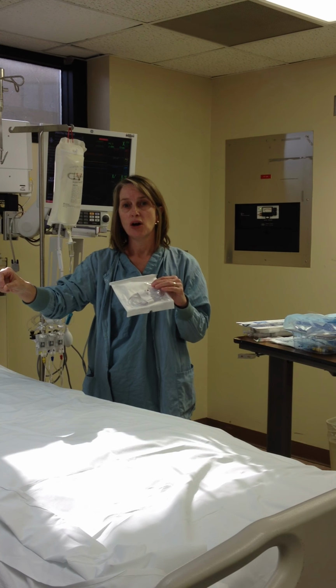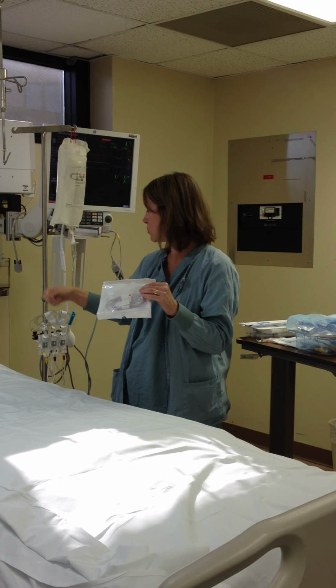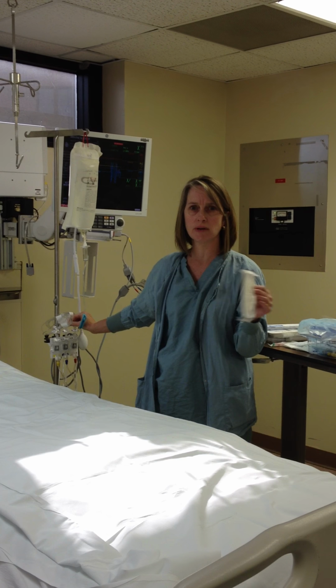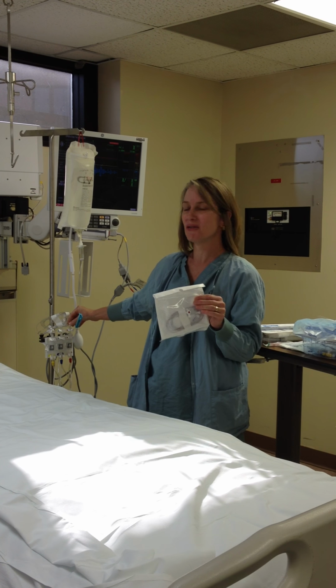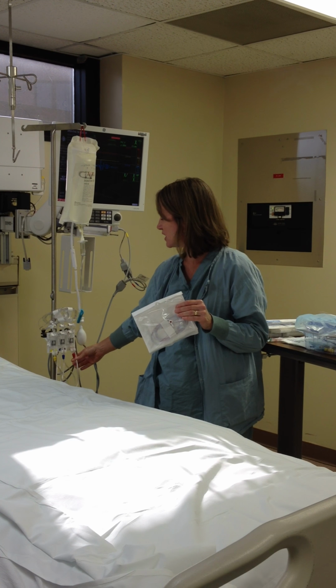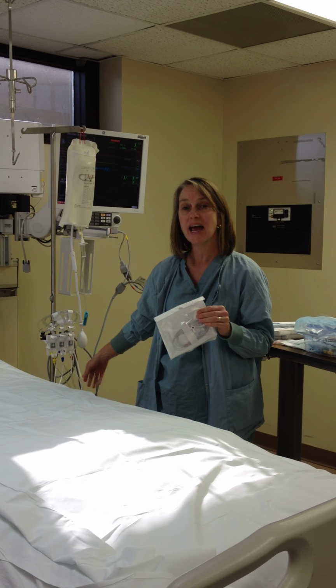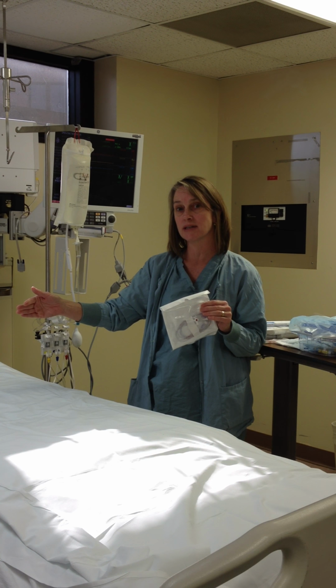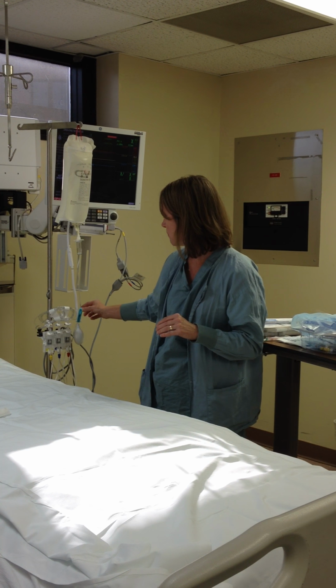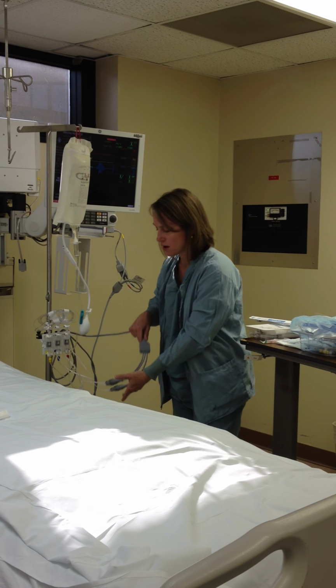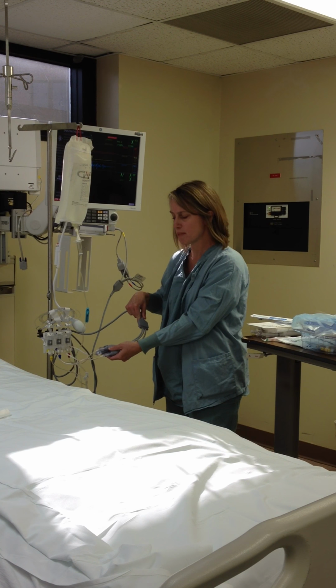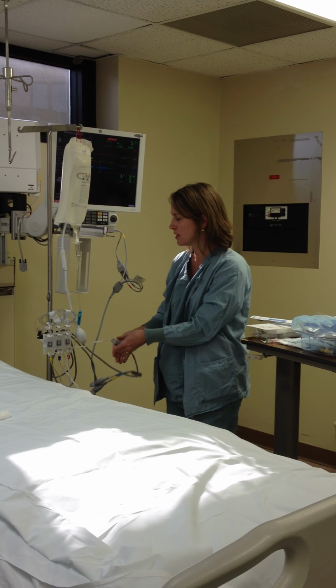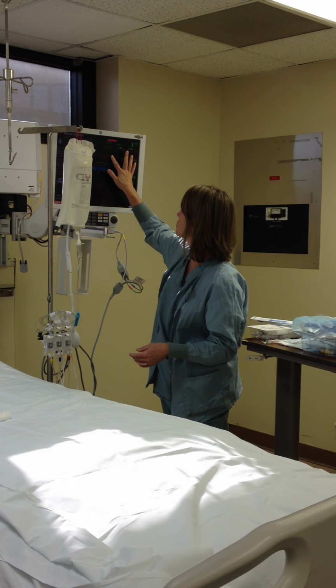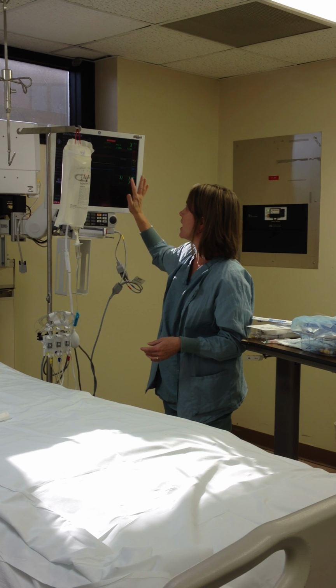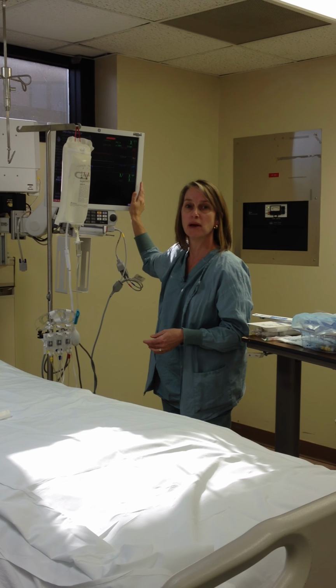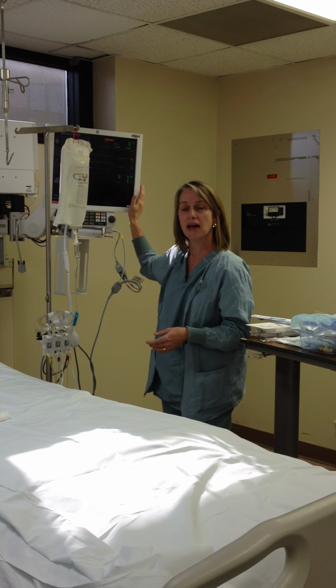He'll actually hook it up, or he'll ask you. Oh, you're going to have to cut that. He'll ask you to hook it to the arterial line transducer area and flush it really, really good before he hooks it up. Once he hooks it up, you make sure that your transducer cables are hooked up. Of course, red being arterial. And you'll get your red line on the monitor, and you'll zero and calibrate everything to make sure that you have a good waveform. And that's basically it.